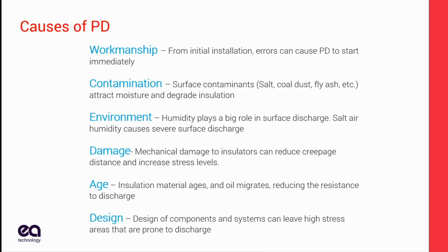Lots of things cause PD. Workmanship is by far the number one, and not workmanship in a negative way. It's not people intentionally doing a bad job. It's not people that don't want to do a good job. But you get workmanship issues where people are not trained. They don't have the right tools. They don't understand the importance of cleanliness.